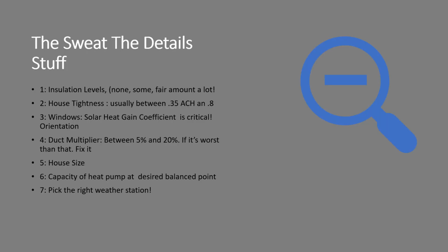This is the detail stuff. Insulation: none, some, fair amount, or a heck of a lot is usually close enough. House tightness is another error we see a lot. ACH, the leakage rate of the house in air changes per hour, is usually between 0.35 and 0.8. It's never 2. I have seen heat loss and heat gain calculations at 2. That's a barn with the door open on a windy day.